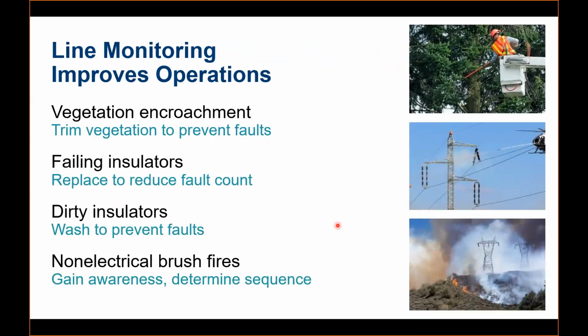Okay. Apart from protection, we have some innovative advantages from this technology, which is line monitoring, or what we call asset monitoring. This could be because of extended vegetation, where plants or trees grow and with the passage of time are going to touch the transmission line, but it's not a fault yet. It's like a fault that's going to happen in the future. Some insulators may not have failed completely, but there is a kind of discharge or some kind of low energy events happening because of bad insulation. Also, dirty insulators can cause low energy events on the lines that may cause the insulator to fail in the future, and also bushfires.